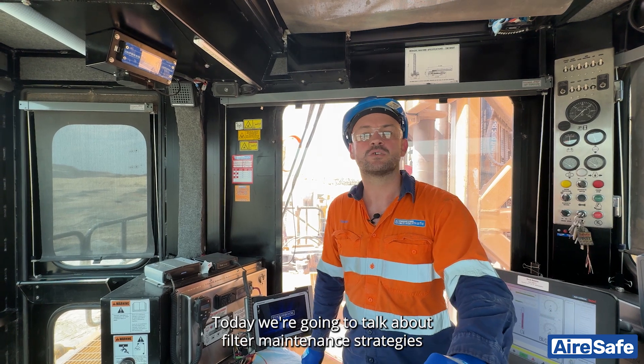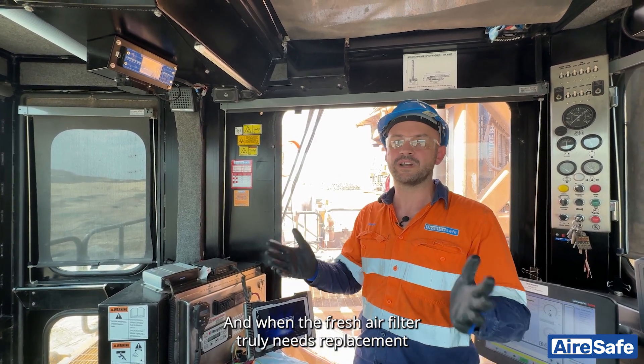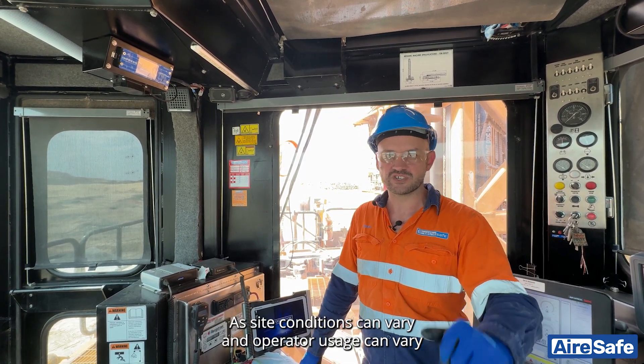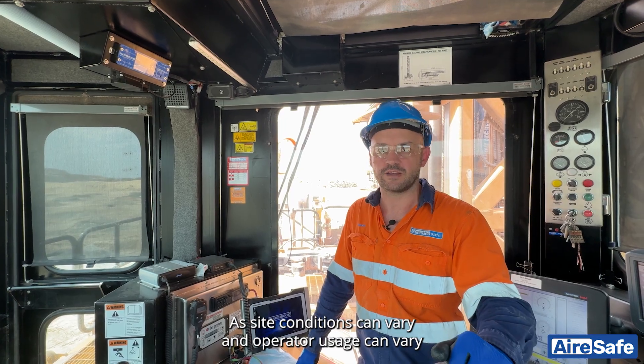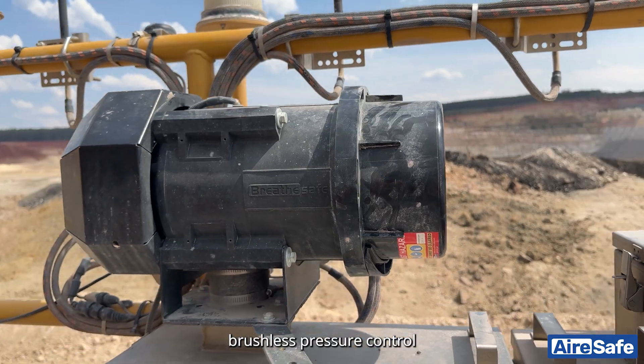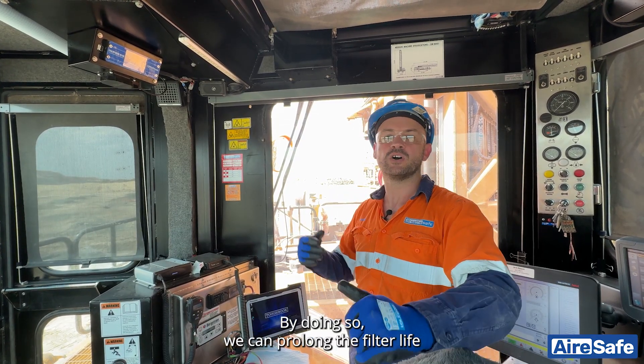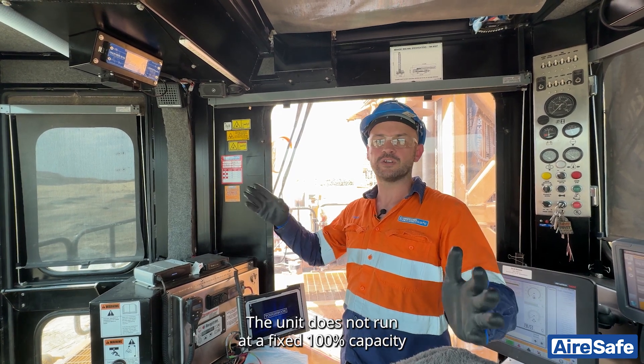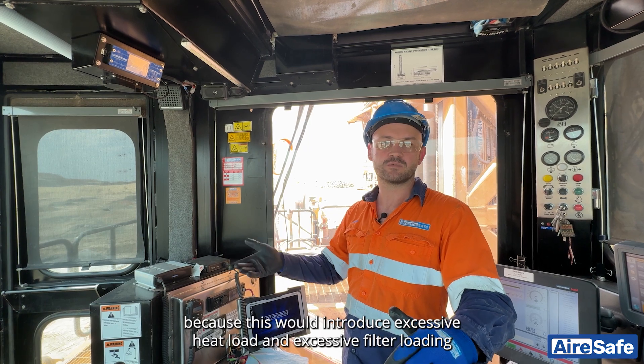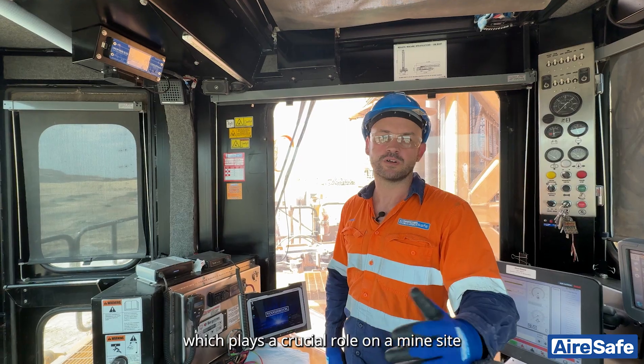Hi, Simon from AireSafe. Today we're going to talk about filter maintenance strategies and when the fresh air filter truly needs replacement. We do not recommend using hours to give guidance, as site conditions and operating usage can vary. We utilize an automatic brushless pressure control. This way we can control the amount of fresh air introduced to the cab, prolonging filter life. The unit does not run at a fixed 100% capacity, as this would introduce excessive heat load and excessive filter loading, which plays a crucial role on a mine site.